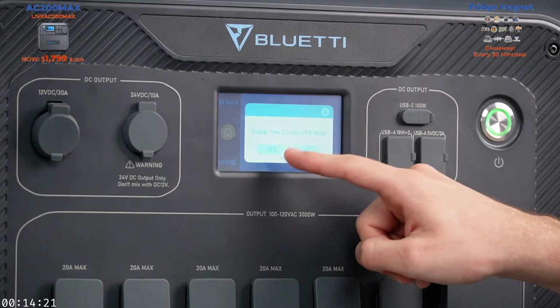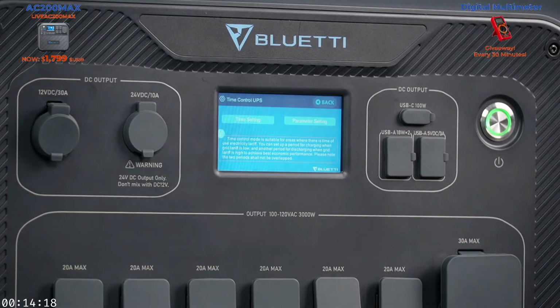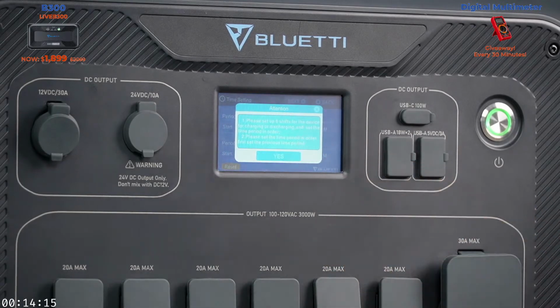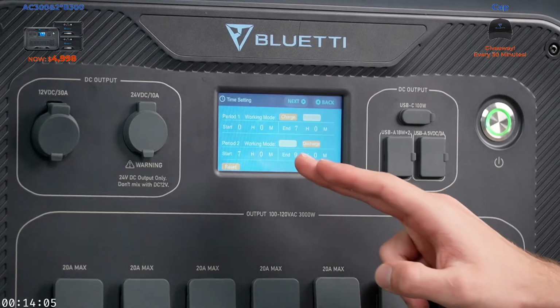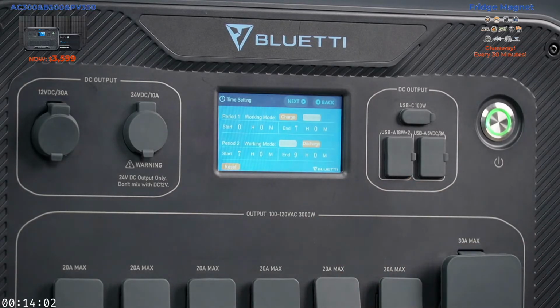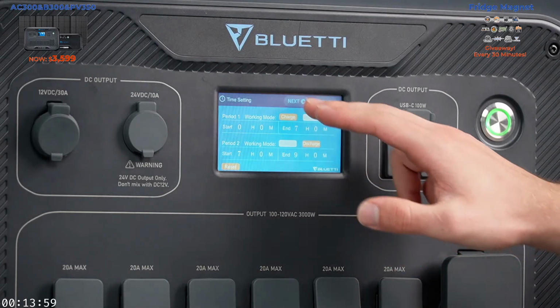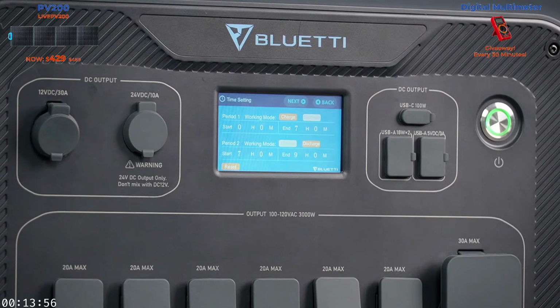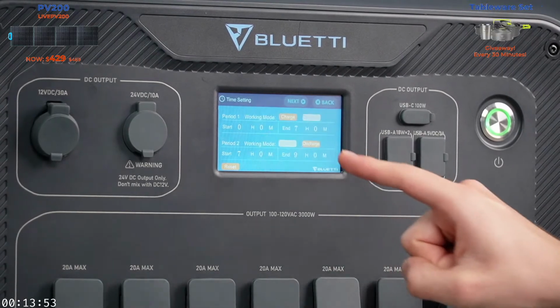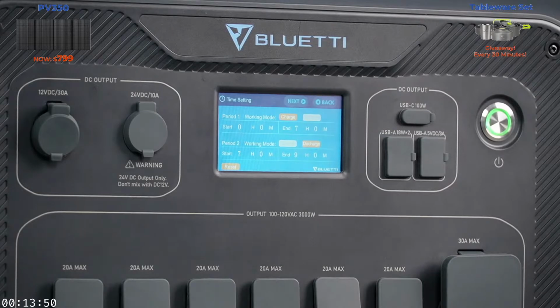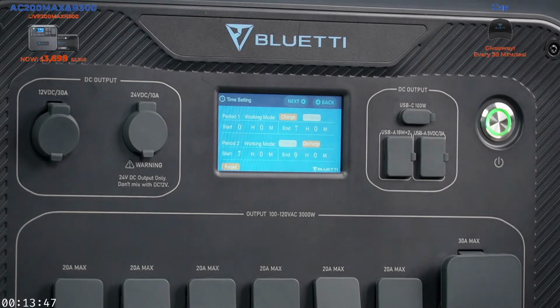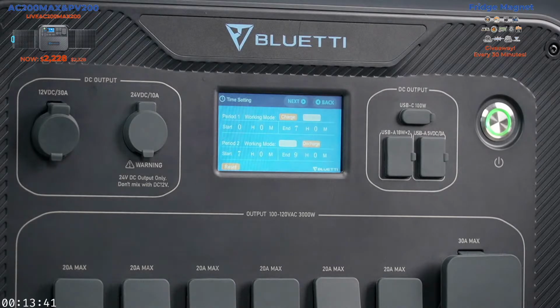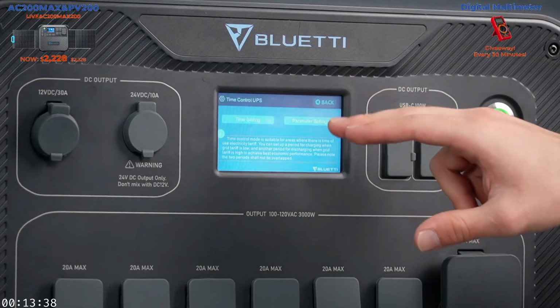Next we have time control UPS. As the name implies, we can control the time - we have the time settings right here. It says please set up to 6 shifts for a device for charging and discharging and set the time period in order. So we have to set period 1, period 2, 3, 4, 5, and up to 6 - when you want it to charge, when you want it to discharge. We would do that because we want to charge it from grid when electricity is cheapest, and discharge it when electricity is most expensive, or at least when we can.